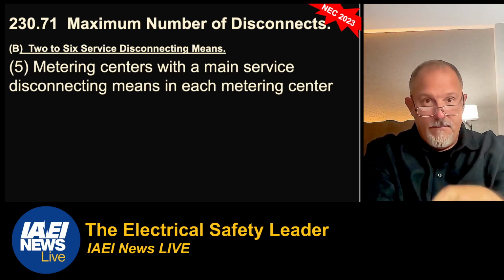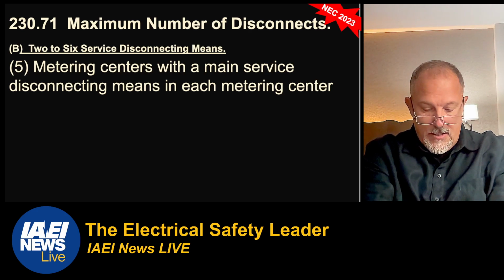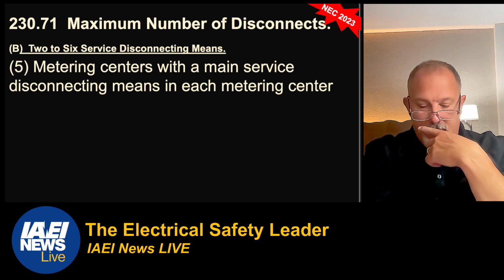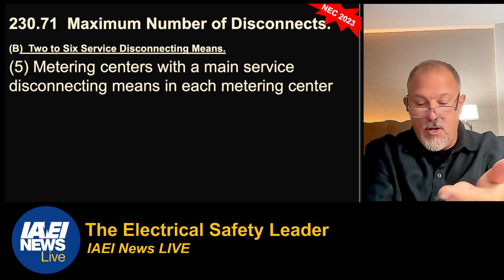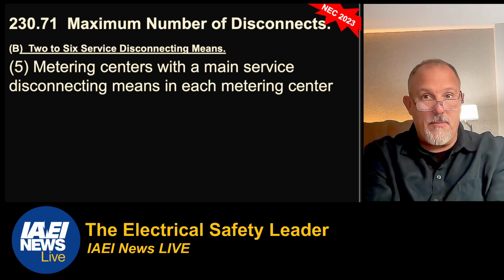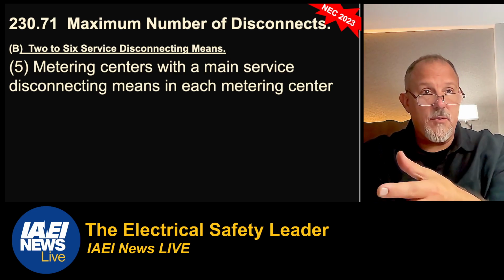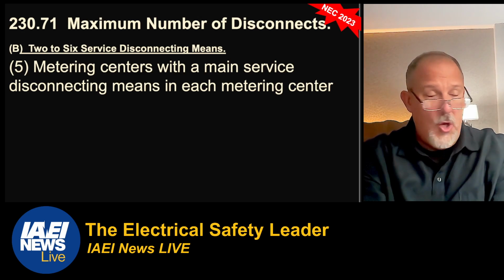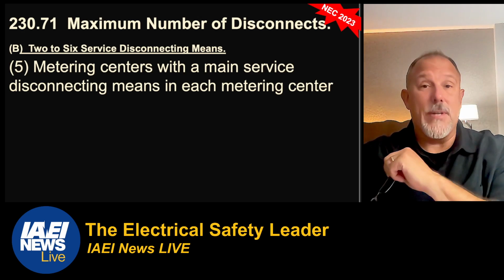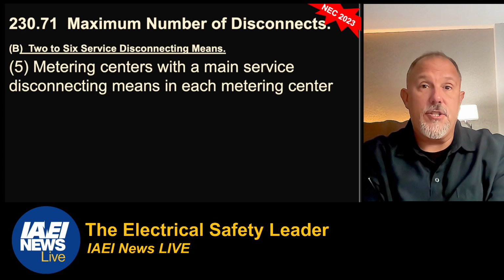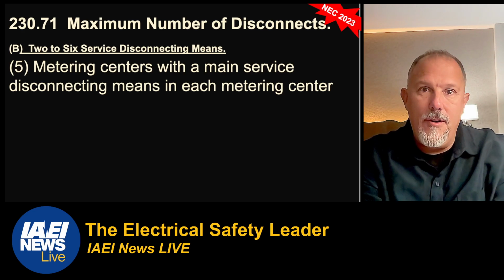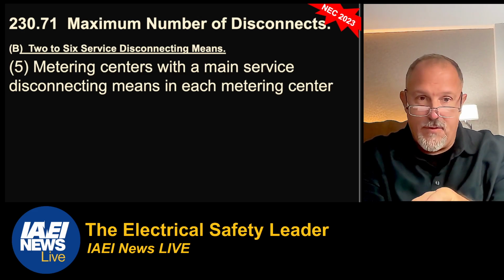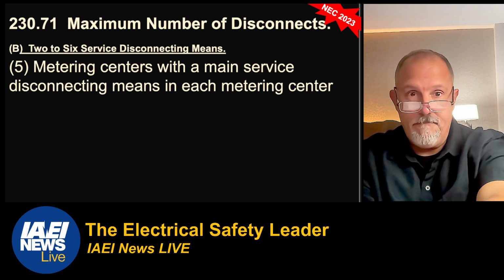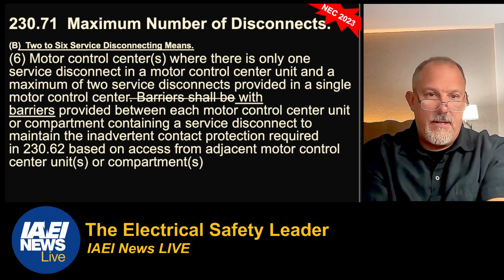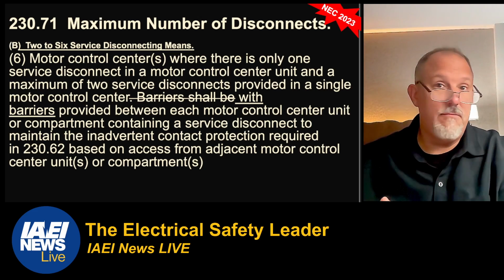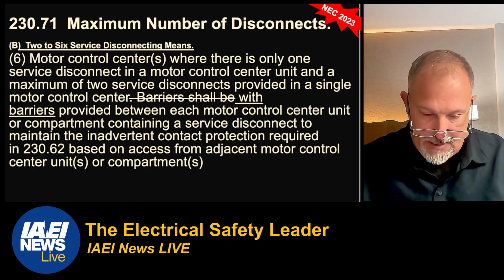Now, we added that in 230.71.5, but we did not remove it from 4, which says service disconnects in switchgear, transfer switches, or metering centers where each disconnect is located in a separate compartment. So that's what we're struggling with right now: how do you create a metering center with circuit breakers in separate compartments? It would be like saying, how do I make a panel board with circuit breakers in separate compartments? I don't know that the standard's going to get there. They're trying, but I don't know that they're going to get there with language that will actually make it manufacturable and cost effective. So with metering centers, be mindful, that's going to be a challenge. If you use meter centers, that's going to be a challenge for you. And this doesn't impact residential, unless you have a house with motor control centers, but most of us don't have that. So anyway.